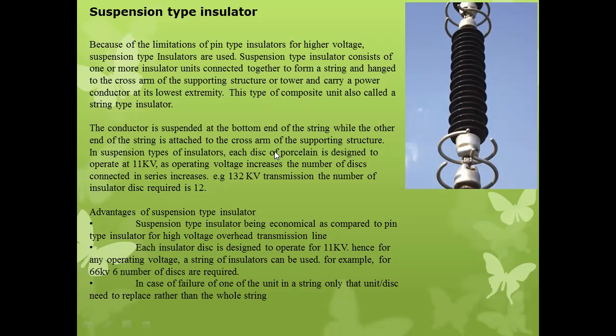So, the advantages of the suspension type of insulator. The suspension type of insulator is economical as compared to the pin type of insulator for higher voltage overhead transmission lines. This is because it can operate for a higher voltage range beyond 33 kilovolt. Each insulator disc is designed to operate for 11 kilovolt. Hence, for any operating voltage, a string of insulators can be used. For example, for 66 kilovolt, 6 discs are required.